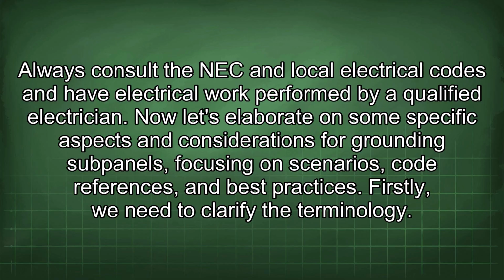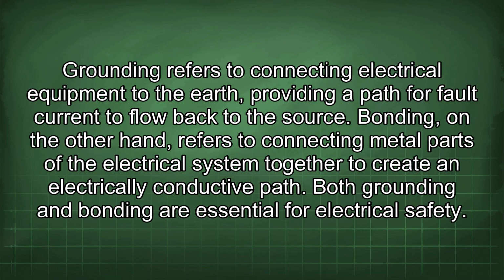Now let's elaborate on some specific aspects and considerations for grounding subpanels, focusing on scenarios, code references, and best practices. Firstly, we need to clarify the terminology. Grounding refers to connecting electrical equipment to the earth, providing a path for fault current to flow back to the source. Bonding, on the other hand, refers to connecting metal parts of the electrical system together to create an electrically conductive path. Both grounding and bonding are essential for electrical safety.